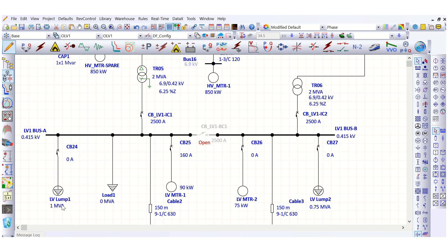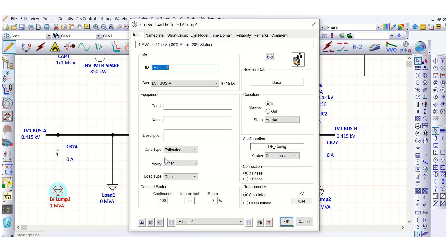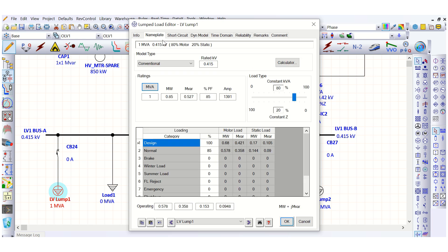First, let's go to the lump load. Under the nameplate tab, the rating is 1 MVA and the power factor is 85%. The load type is set to constant power (constant kVA) at 80% and constant impedance at 20%. This means 80% motor load and 20% static load is considered.